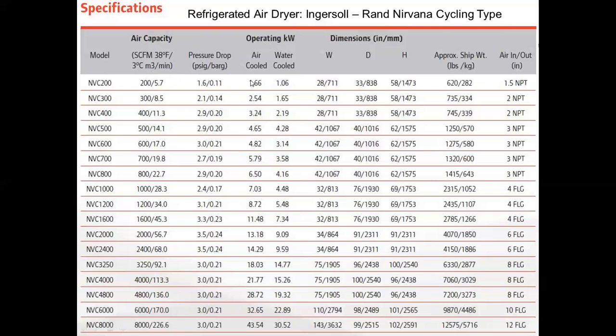Operating kW: you see the air-cooled unit, so this includes a fan in it, is 1.66 kW for this little guy, versus a water-cooled unit. This is on the refrigeration system in the refrigerated dryer. So you could have an air-cooled condenser in there or a water-cooled condenser, and you're not running that fan, and you may get a little better heat transfer in a water situation than an air situation. Now, if you're going to do water cooled, there is a pump someplace that has to pump that, and they don't include the pump energy here. So it's not the whole picture. Not really a totally fair comparison, even though we can move liquid for a unit mass a whole lot more efficiently, or with less power, than we can move air.